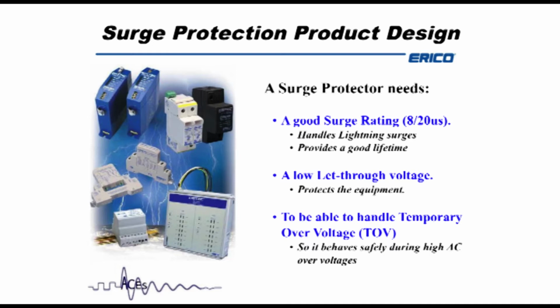We're very much trying to control the voltage coming in through the switchboard out to the load. Now these voltages are not 50 hertz overvoltages, they're surges - very short duration, sometimes only a few microseconds at a time, but quite often very high magnitude, some tens of thousands of volts, but very short duration.